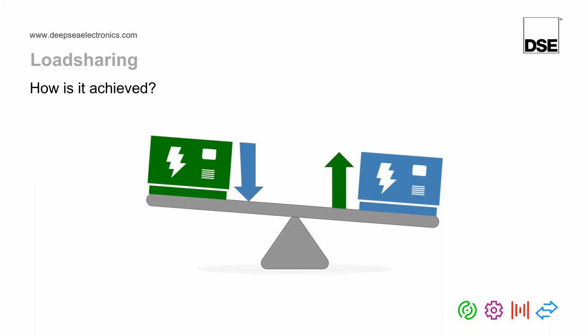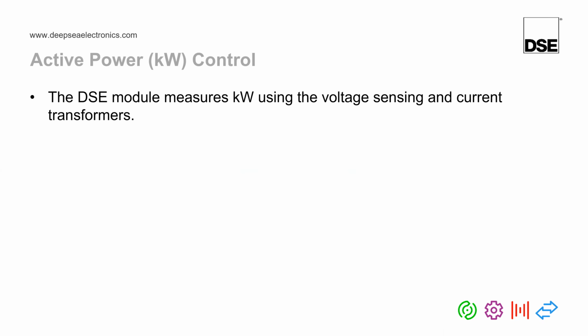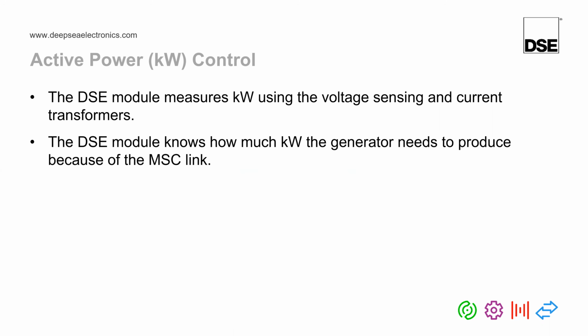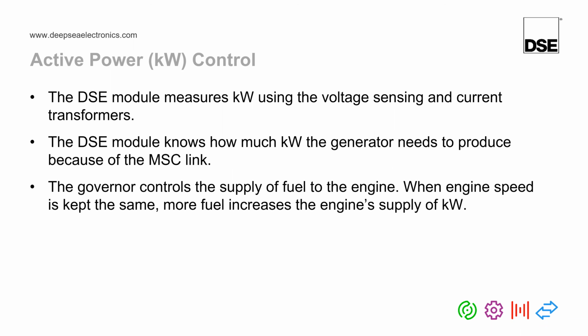Now, the way in which the DeepSea module does this is we actually have two different types of power we need to control when doing load sharing. The first type of power is something called active power, which most people will know as kilowatts. Now, the DeepSea module measures the kilowatts the generator is producing by using voltage sensing and the current transformers, which you wire into the DeepSea module. The DSE module then knows how much kilowatts that generator has to produce due to the MSC-link communication between the generators. And then the way the DeepSea module controls how much kilowatts the generator needs to produce is by using the engine's governor. So you can see that again, the engine governor is coming into play here. So we actually use the engine governor for both frequency control, phase control, and also kilowatt control.